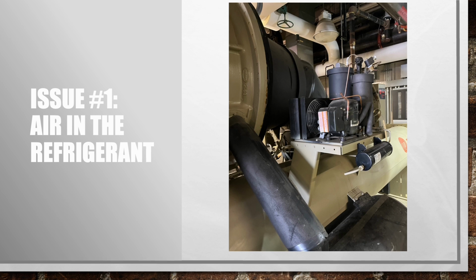So that's why it has this purge unit. The purge unit pulls all the air out of the system and rejects it after it goes through its purge cycle. It's not super common that you have a lot of issues with the purge units, but it does happen. Typically, air will get in the system via leaks, and since the system's in a negative pressure all the time, it's sucking air in instead of pushing gas out.